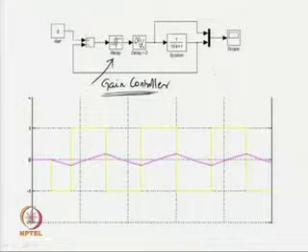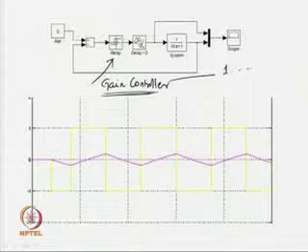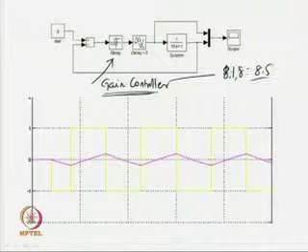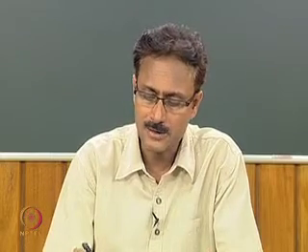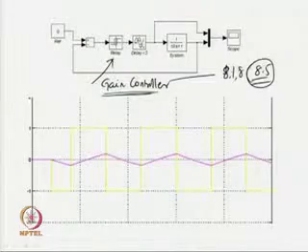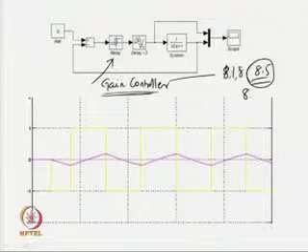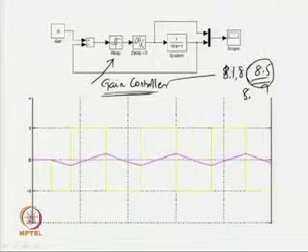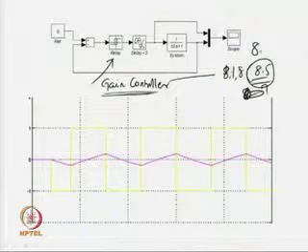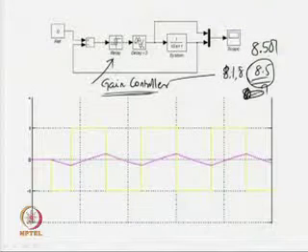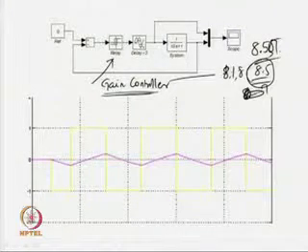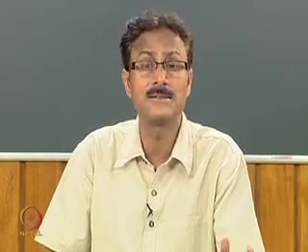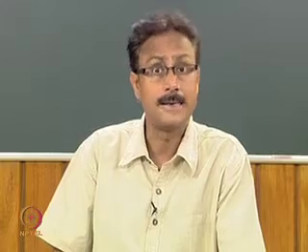You will spend much time obtaining the correct gain value. And if by mistake you exceed that value by even a small amount — say 8.501 instead of 8.5 — the output will be unstable or unbounded. There is risk involved with the gain controller. To avoid that, a relay is used in the closed loop, which guarantees sustained oscillatory output irrespective of any non-zero relay setting.